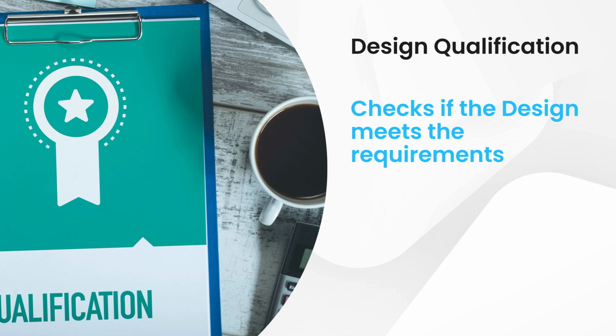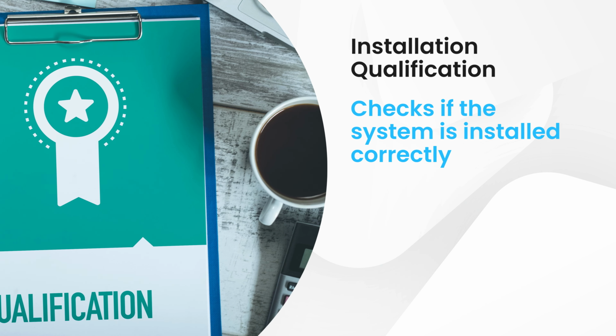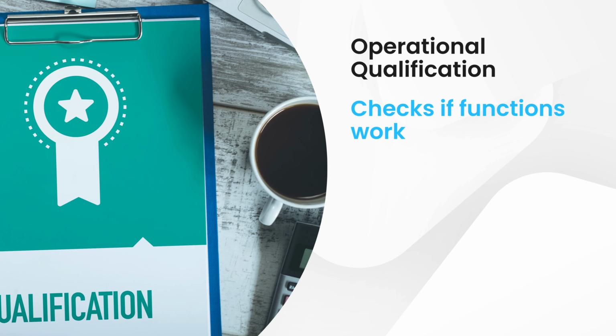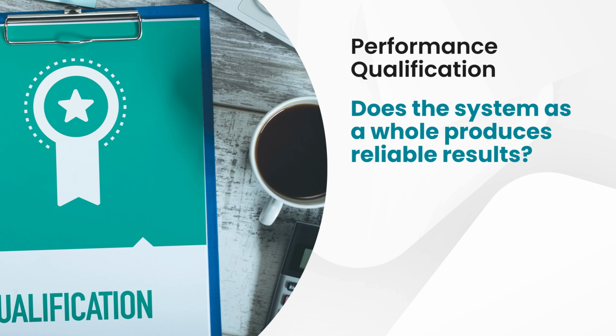2. Installation qualification, IQ. This verifies that the HPLC system is installed correctly according to the manufacturer's specifications. This includes proper connections, environmental conditions, and software installation. 3. Operational qualification, OQ. This demonstrates that the HPLC system performs as expected within its operating range. You'll test key parameters like pump flow rate, detector accuracy, and temperature control. 4. Performance qualification, PQ. This confirms that the entire system, including the instrument, software, and your specific analytical method, consistently produces reliable results for your particular application.